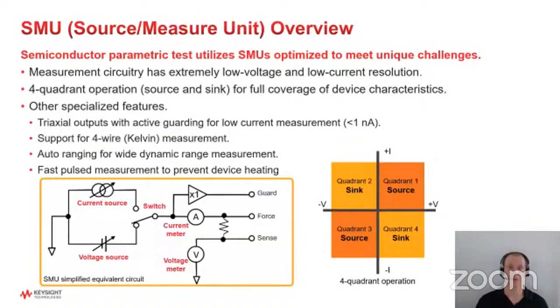In parametric tests, the fundamental unit, or module, that we use to measure things is the source measure unit, or SMU. As the name implies, it can both source current or voltage and, at the same time, measure both current and voltage, independent of what it's sourcing. These typically have very low voltage and low current resolution, as I just talked about. As you can see here, in the parametric test world they're also typically 4-quadrant devices. We can source and sink current in all 4 quadrants shown there. That's important because we not only want to supply positive current and voltage, but sometimes we want to apply a negative voltage and see a breakdown current, which typically shows up as a negative current.